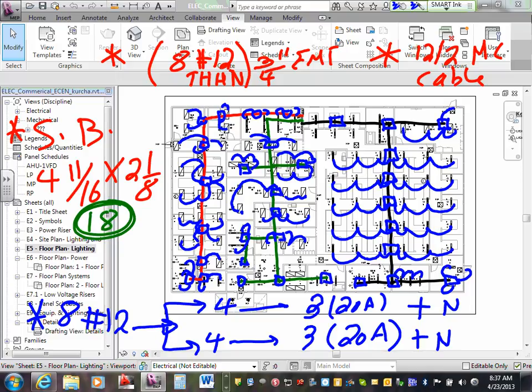So I'm going to put my conduit. My conduit is coming right in here from box to box to box, right? So here's my box sitting here. Then inside this bathroom, guys, I loop. Can you see the 2 fixtures? I use an MC or a fixture whip. If you're within 6 feet, Jeff, as you know, if you put your box right here within 6 feet, you use the fixture whip that comes with it. So when I put my box right here, I will use a fixture whip or take it as an MC cable from these 2 fixtures directly into this box. Cool? So I have my box right here, picking up these 2. I have another bathroom, I put another box here to pick these 2 as it goes to the panel.